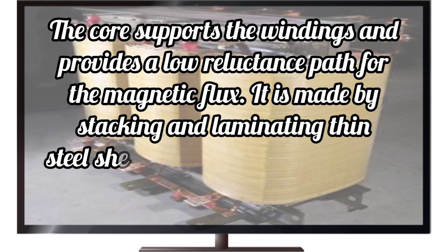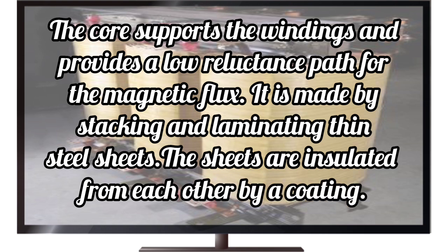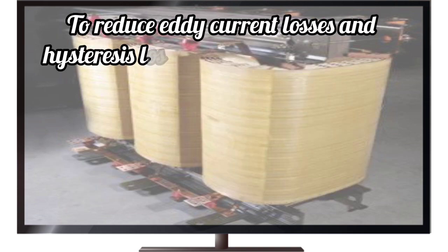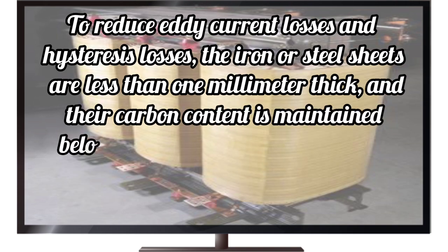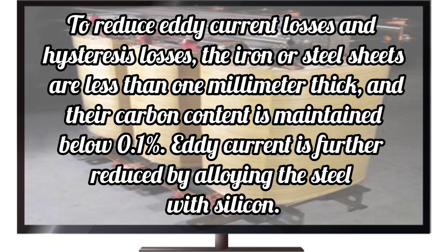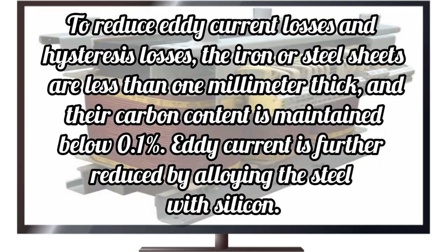Core and winding. The core supports the windings and provides a low reluctance path for the magnetic flux. It is made by stacking and laminating thin steel sheets. The sheets are insulated from each other by a coating. To reduce eddy current losses and hysteresis losses, the iron or steel sheets are less than 1 mm thick, and their carbon content is maintained below 0.1%. Eddy current is further reduced by alloying the steel with silicon.